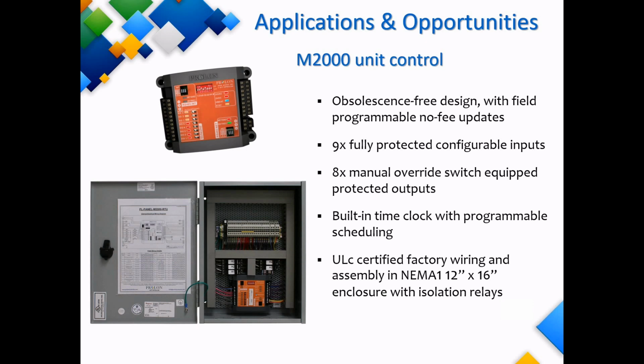The M2000 has 9 inputs and 8 outputs, 5 of which are digital and 3 of which are analog outputs. All outputs have handoff auto switches to help contractors with troubleshooting if they wish to manually override some outputs. The controller also has an internal time clock with scheduling and holiday calendar.